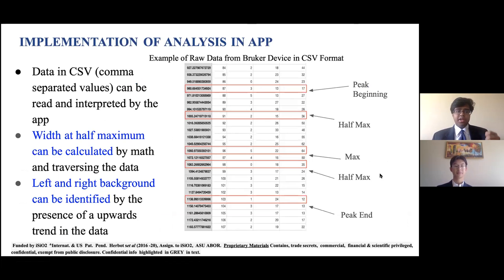To implement this in our app, the data must be put into a format called CSV, or comma-separated values, a simplified form of which is shown on the right side. The rightmost column contains the y-axis values — the counts of each element for each energy level — and the second column contains the x-axis channel numbers relative to energy. From this raw data, we can find the maximum, half-max values, and the beginning and end of each peak. Once the application has all this information, it will run the mathematical algorithm we described, but operating directly on raw data.